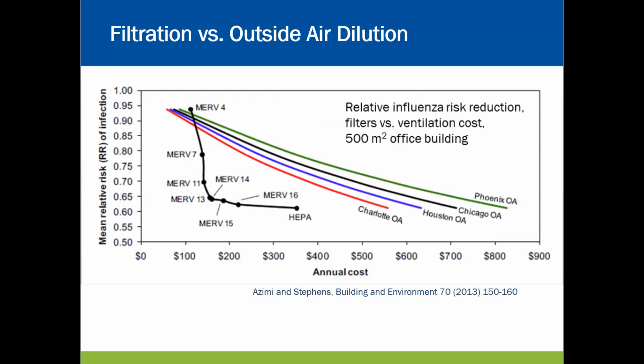So filtration versus outside air dilution. This chart shows the cost of changing filters on an average size little office building, and what that does to this index that has been created. It's like a relative risk of getting an infection. So really high risk of infection if you have poor filtration, like a MERV 4 to a 7.